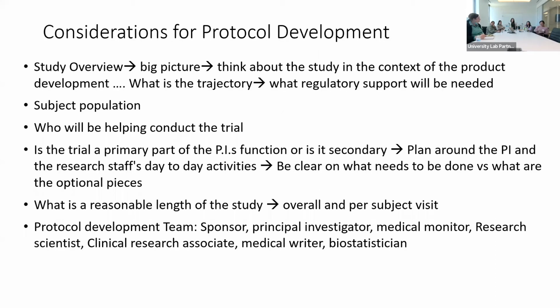Some of just the basic considerations: think about the big picture, right? With your product, where is it going? What is your plan for your product, your device, for the next 5 years? Is there anything you can implement in this initial study to help support a regulatory submission down the line? Is there a usability piece that you can incorporate?